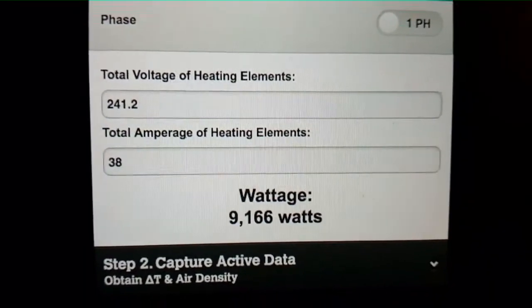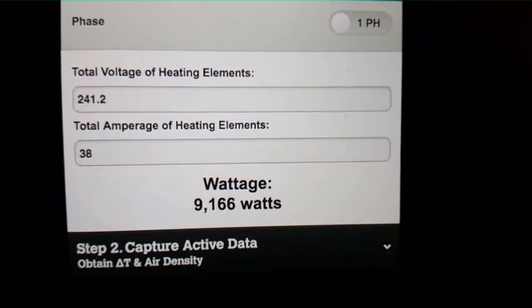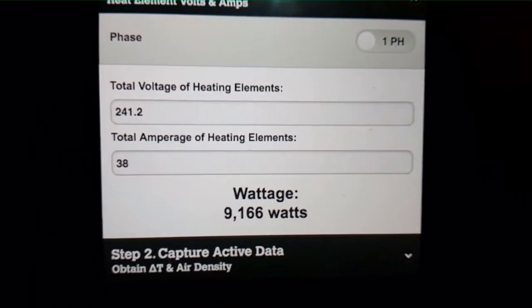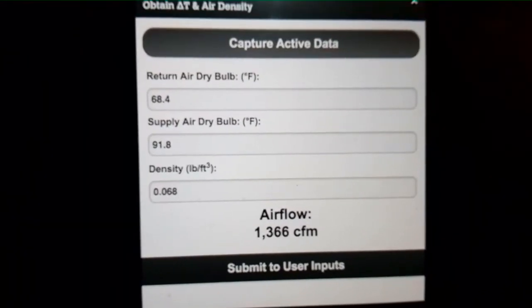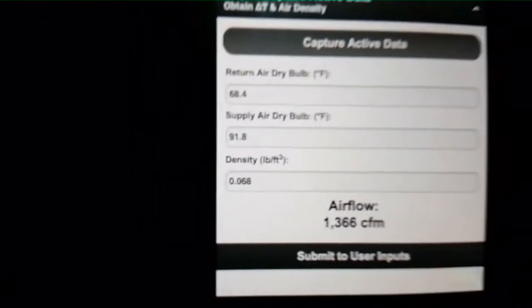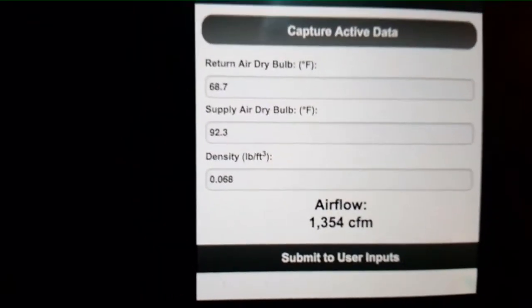Guys, I have an i-Manifold probe around the corner from the heat strips here. I have one inside the machine and then return in. And what I'm doing, taking measurements, we have, let's see if I can get closer. See if we can get focused. We have the total voltage of the heating elements at 241.2, the total amperage, 38, 9166 watts. We go in to capture the active data, and all that means is the i-Manifold app is capturing data from the machine. We can go ahead and do that again, 1354.